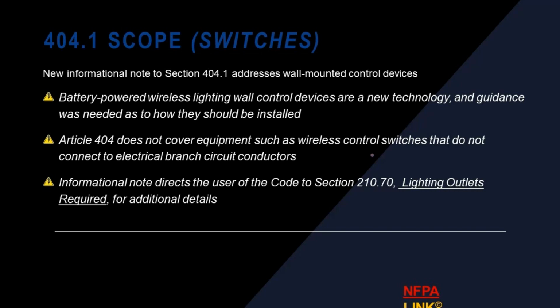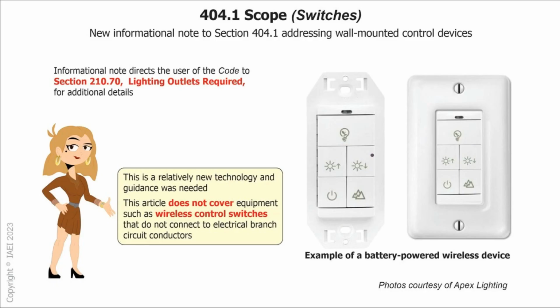There is a 2023 code change: 404.1 addresses wall-mounted control devices. Battery-powered wireless wall control devices are new technology and guidance was needed on how we can install them. 404 does not cover wireless control switches that do not connect to electrical branch circuits. The informational note directs the user to code section 210.70 for lighting outlets required. So we're starting to get into these battery-powered switches for code purposes.